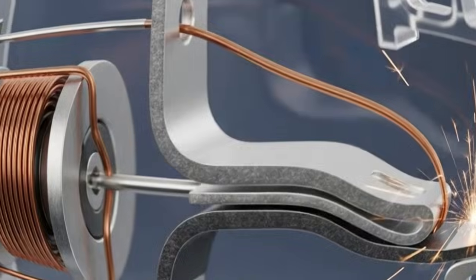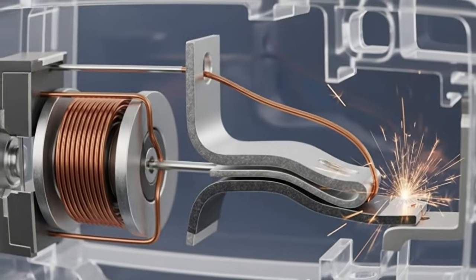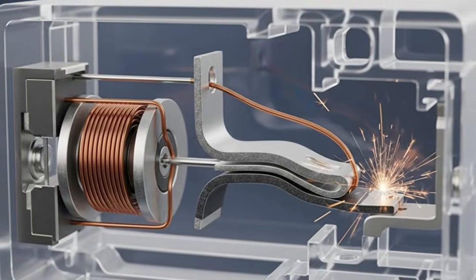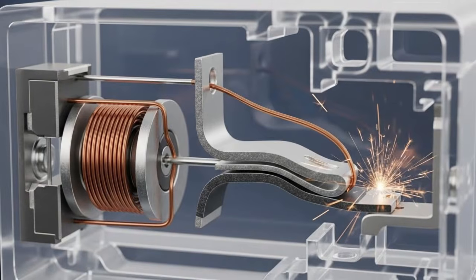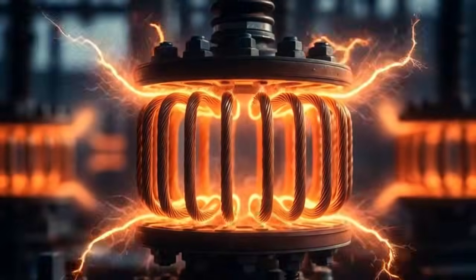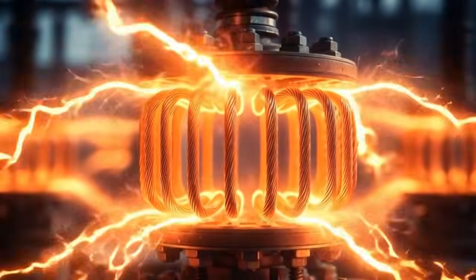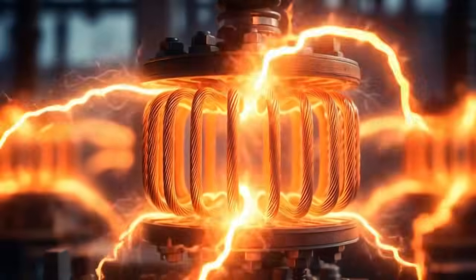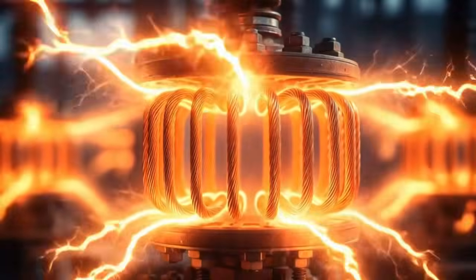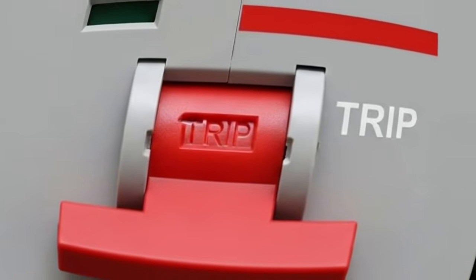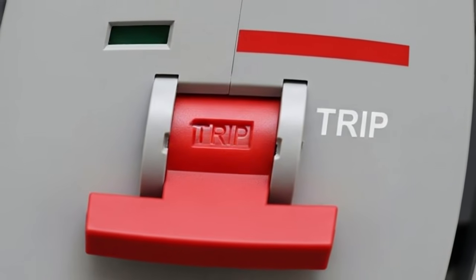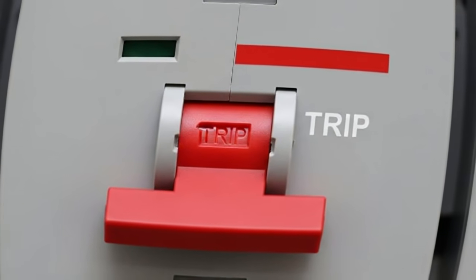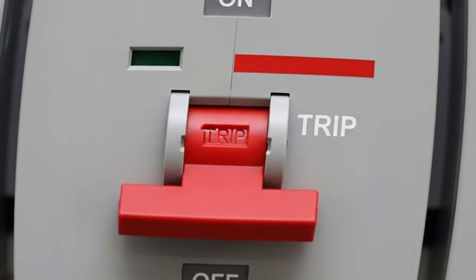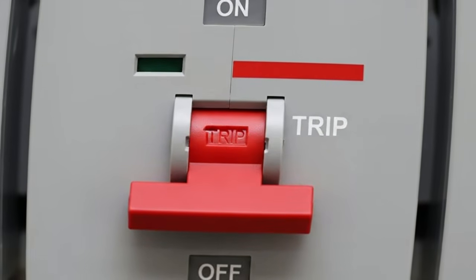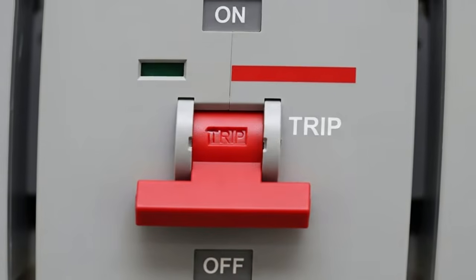Inside the breaker, 2 mechanisms work together to detect problems. A bimetallic strip heats up and bends when excess current flows through it. This handles slow overloads. An electromagnetic coil reacts instantly to sudden current surges. This handles short circuits and ground faults. When either mechanism activates, a spring-loaded switch inside the breaker snaps open. This physically disconnects the circuit from power. The breaker handle moves to a middle position between on and off, the tripped position.